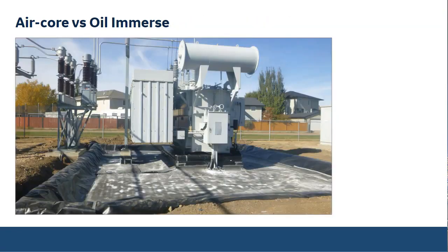This is a picture of a traditional oil-filled unit, and I just wanted to show the base tank of it, because just to create that base containment tank requires a lot of energy, time, and money. There are several layers of materials, and it's quite expensive. And this is just to contain a leakage. And if there is a leakage, then you have to change and replace some of these materials, which can also be very expensive. If you're designing, for example, a pad for an air core reactor, the only precaution you would need to have is related to the magnetic field, which I'm going to mention on the next slide. But this is how simple the air core technology is compared to an oil-filled unit.